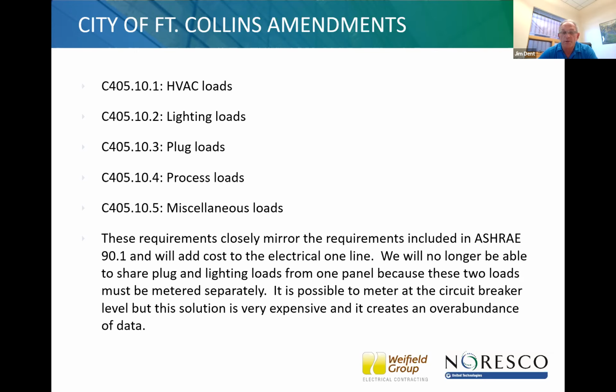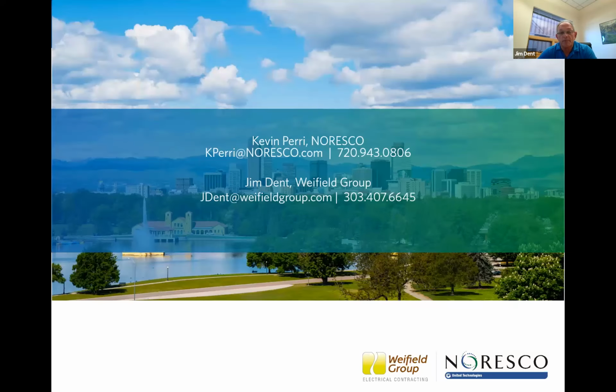We did a job in Grand Junction where we actually had to meter plug load at the circuit breaker level to meet the metering requirements, and that's very expensive, and it creates a horrible amount of data. So your one line, you're just going to have more panels than you would normally have. So just be prepared for that in the city of Fort Collins, because you've got to meet the ASHRAE 90.1 metering requirements. Next. And Jim, I'll add, remember in Boulder, they wanted to know how to access all that metered data as part of their commissioning plan. So I would imagine Fort Collins would go there next. Yes, absolutely.